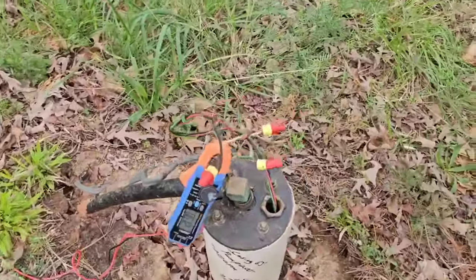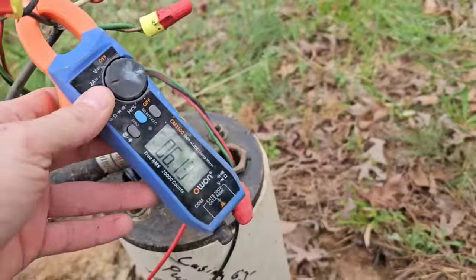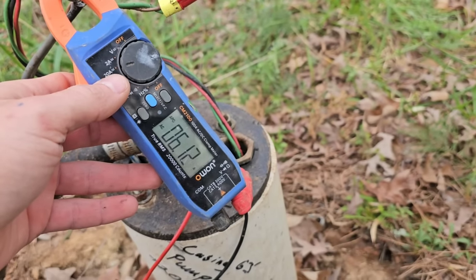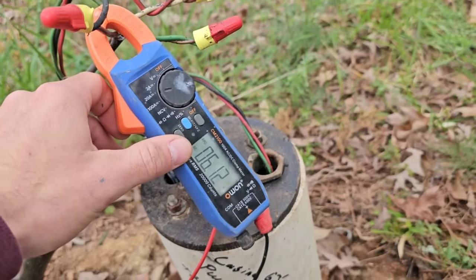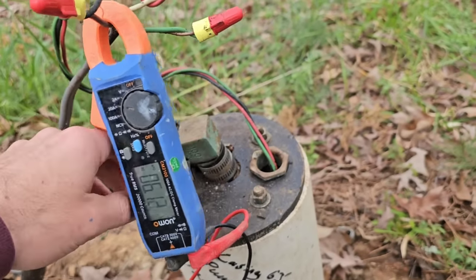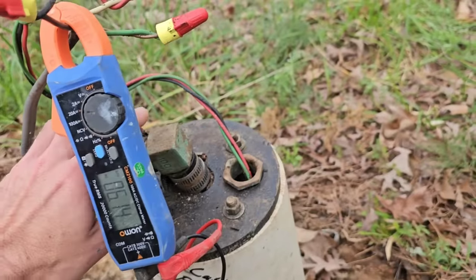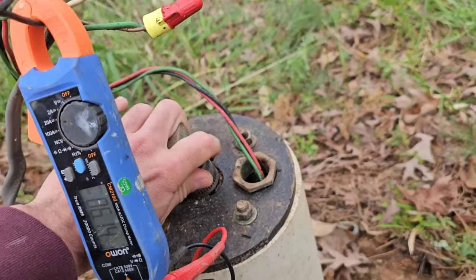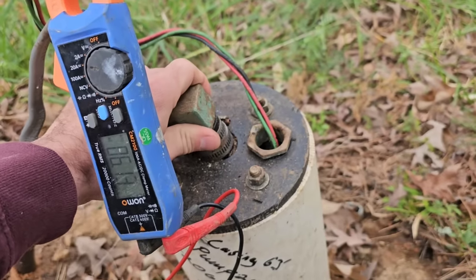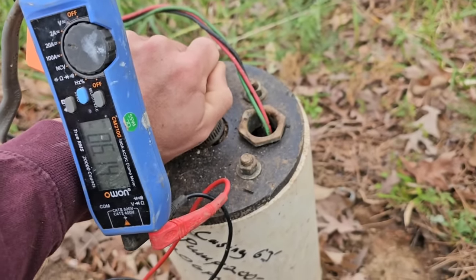Okay, now we've been here for 10 minutes. I was trying to run the system, let it cut off, and that way I could disconnect the wire nut. Since no one's here, I can't get inside to flip the breaker off. I was running some water at the house and it was kind of weak pressure. Then I came over here and I grabbed this 90. Typically when you're dealing with well water, you're dealing with 55 degrees. This elbow here is warm.